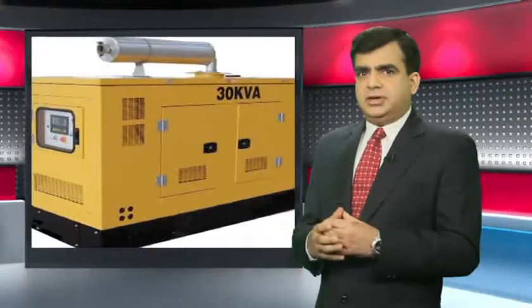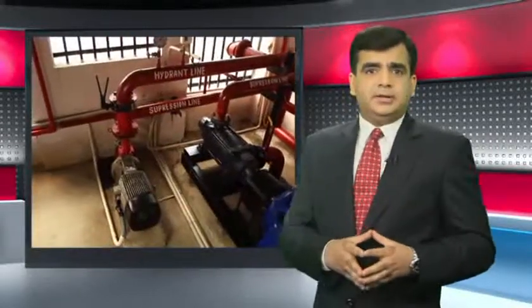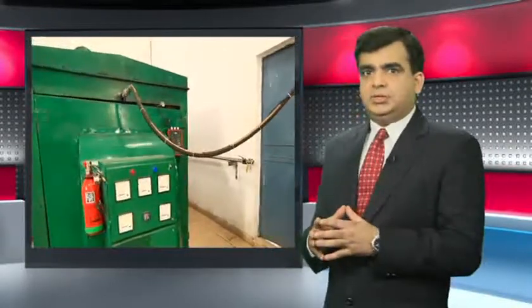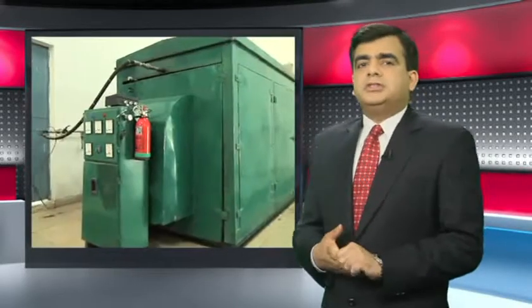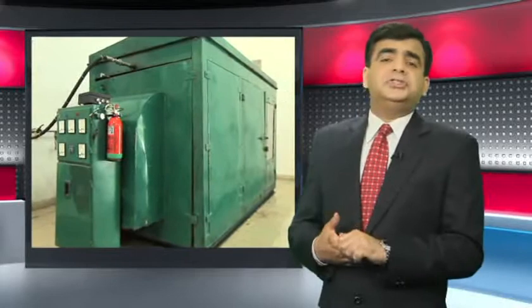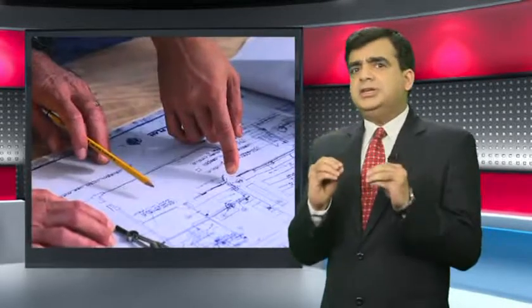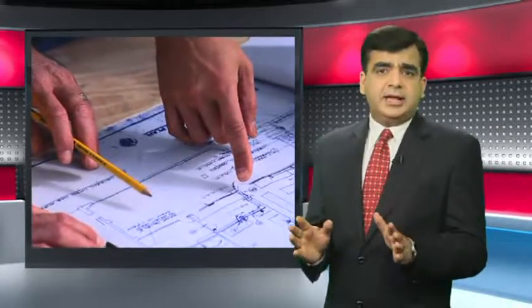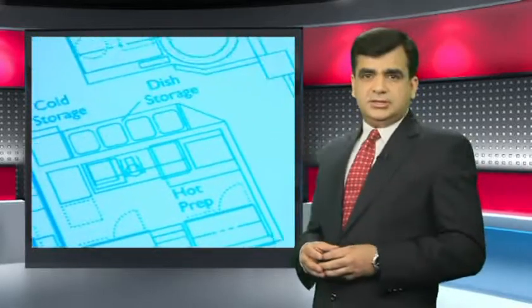For a larger generator, the water is supplied from a pump and a water reservoir or tank. We call it a pump-based auto-quell system. Now, this is how the pump-based auto-quell setup looks like in real life. The auto-quell system has been set up according to a design provided by the Ceasefire design cell, which studies the needs and vulnerabilities of the area at length. Do keep in mind that the setup may differ as per the variations of the applications.